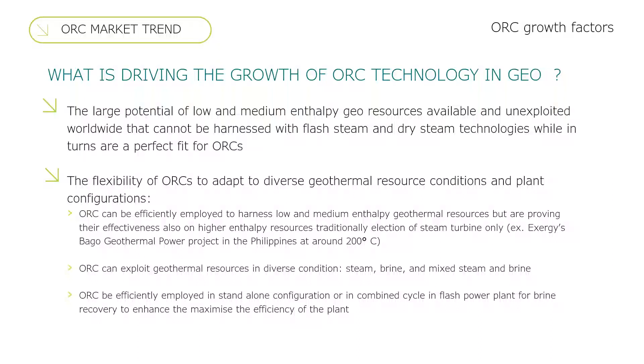For example, in our power plant in the Philippines, the resource temperature we were using is around 200 degrees. ORC is very flexible because it can be used mixing different resource conditions — steam, brine, or mixed steam and brine resources — which allows great flexibility in plant operation. ORC should not be seen as the only technology, but can also be a good complement in new plants, in combined cycle with a flash plant, increasing the efficiency of new wells.